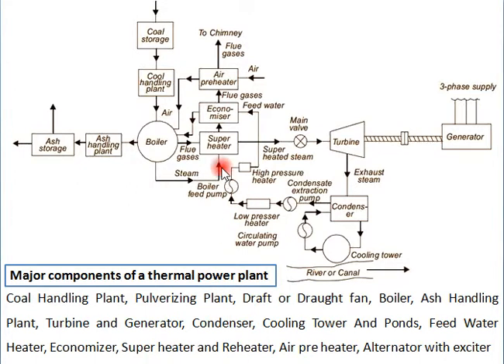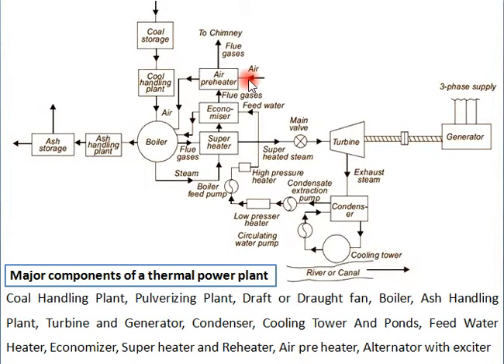The super heater receives steam produced inside the boiler, where its temperature is raised further and it is converted into superheated form with the help of flue gases. After that, the air preheater raises the temperature of atmospheric air used for the combustion process inside the boiler, using flue gases passing through the air preheater. This atmospheric air, with raised temperature, comes to the boiler and takes part in the combustion process.